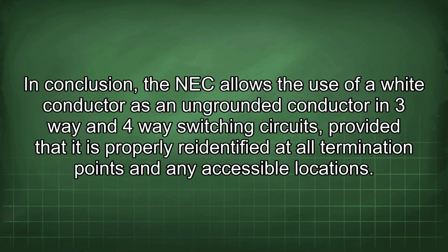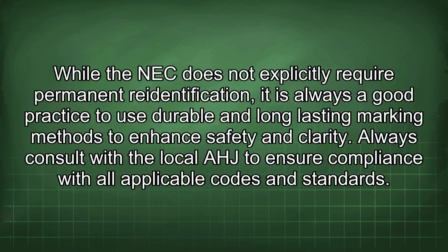In conclusion, the NEC allows the use of a white conductor as an ungrounded conductor in three-way and four-way switching circuits, provided that it is properly re-identified at all termination points and any accessible locations. While the NEC does not explicitly require permanent re-identification, it is always a good practice to use durable and long-lasting marking methods to enhance safety and clarity. Always consult with the local AHJ to ensure compliance with all applicable codes and standards.